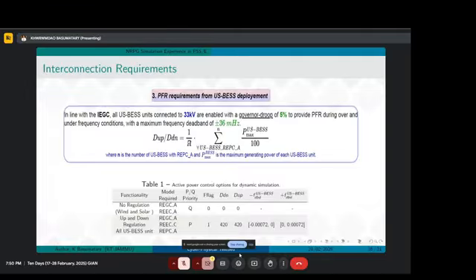The interconnection requirements from the Indian Electricity Grid Code say that utility scale batteries should be connected to 33 kV and enabled with a governor droop of 5% to provide primary frequency response during over and under frequency conditions, with a maximum frequency deadband of plus minus 36 millihertz. This is the formula used to coordinate and share power from different battery energy storage units, and there is a table showing the different configurations adopted during simulations for down and up regulation, with different frequency deadbands in the battery energy storage systems displayed in the table.